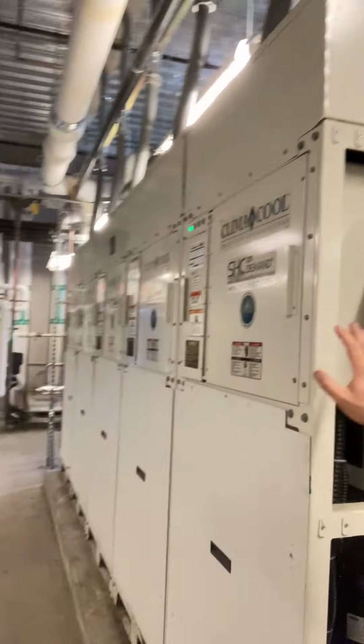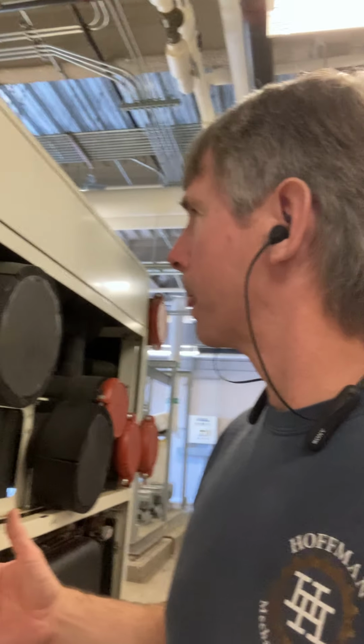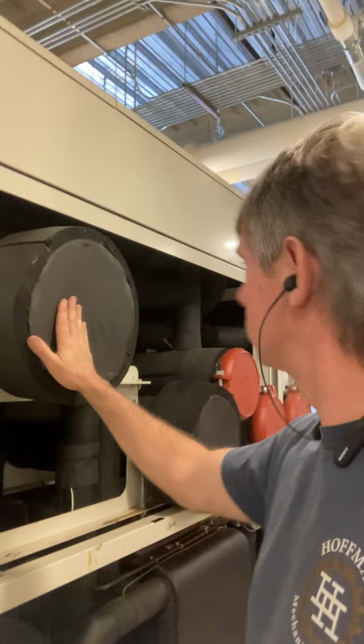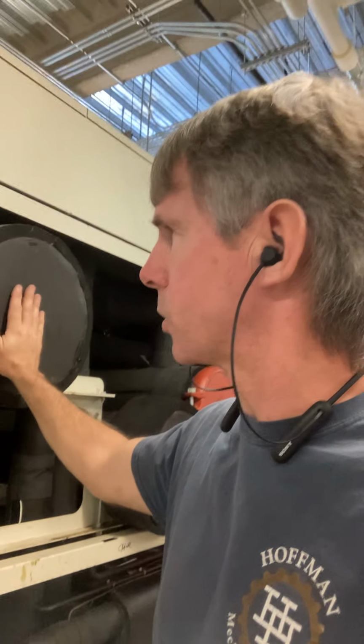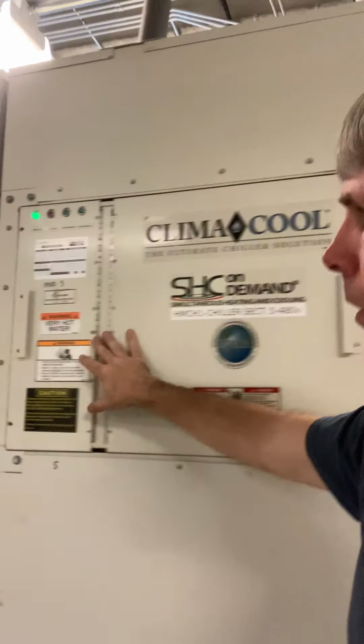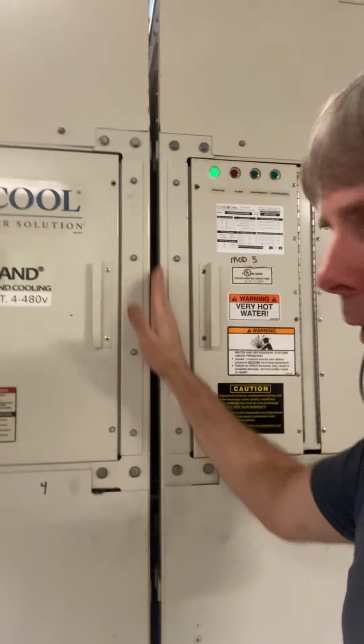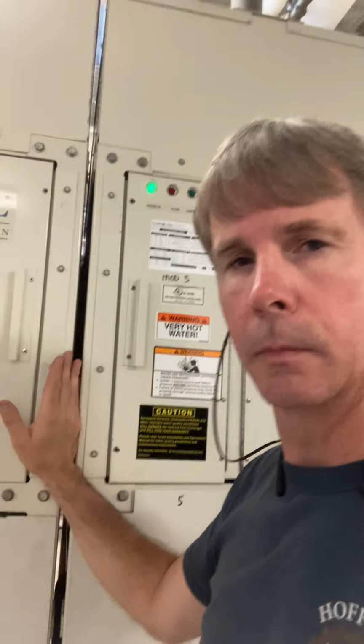Basically, these chillers actually come separate to the job site. They have main 6-inch water headers, and I believe these are 8-inch. I'm sorry, these are 85-ton models, so they have 8-inch headers. It's very loud in here. All of those get coupled with Victaulic fittings, so that you basically have one long, consistent run of piping for these models.